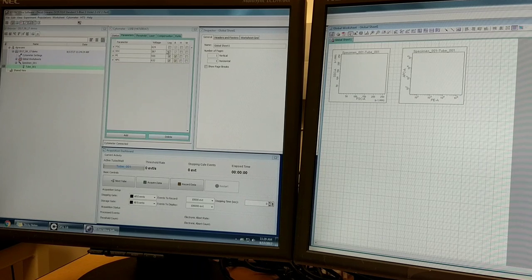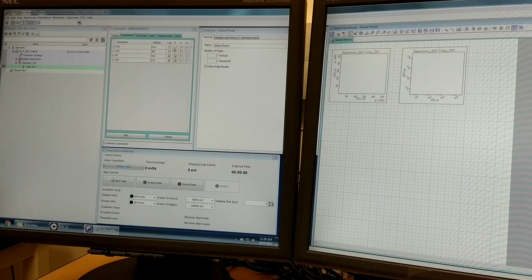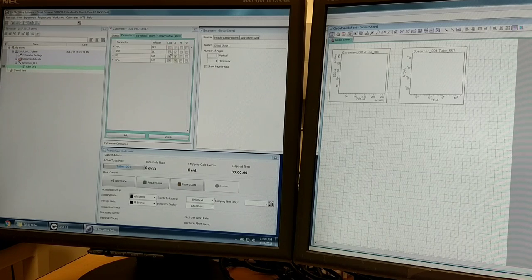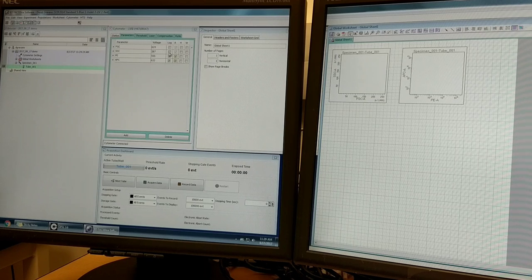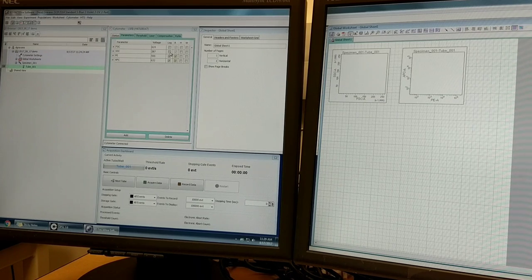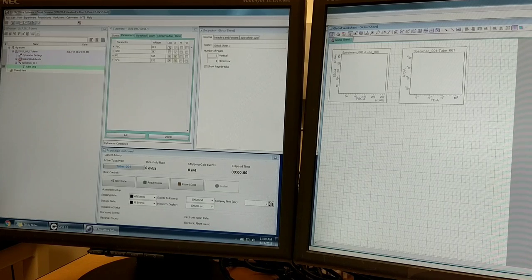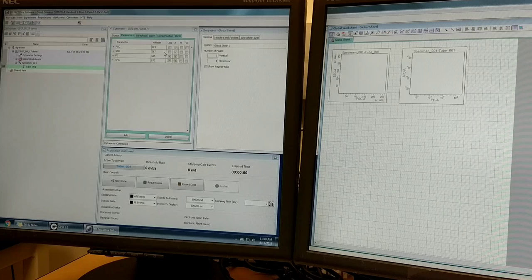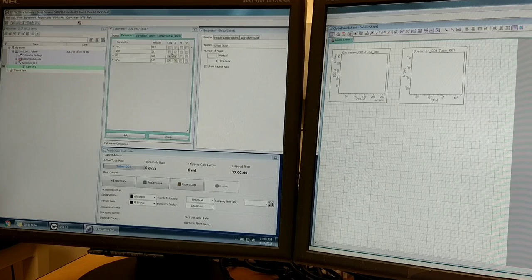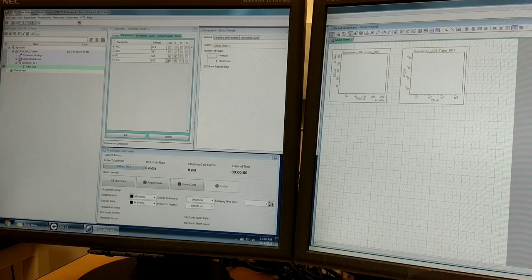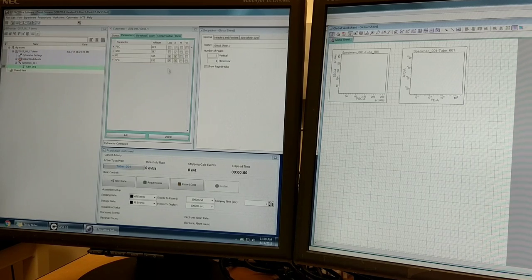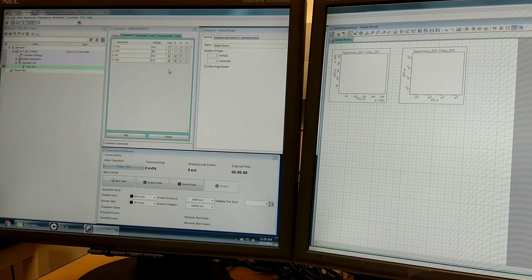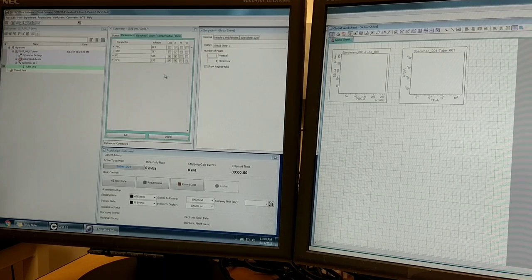Now I'm going to come back to the parameter tab. It currently has forward and side scatter with the log box unchecked, meaning it's going to record them in linear scale. That's fine for me. Some individuals choose to look at side scatter in log scale and rarely some like to look at forward scatter in log scale. But I'd say 95% of the time, these log boxes would be unchecked.